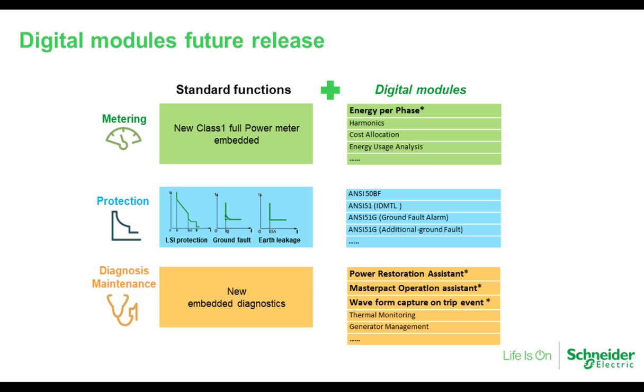Some of the other things, with addition of more relay capabilities within new breakers, there's more protection. Original breakers, if we all remember, old electromechanical trip devices were built into low voltage breakers. Now with new digital modules, we can add metering, we can add additional protection, and we can also add diagnostics to the trip systems. With new integrated relays capability, we can get class 1 power metering down to 1% accuracy. We have embedded diagnostics that the customers have more insight to how the breaker will perform or is performing, which would allow for better maintenance and planning for the future.